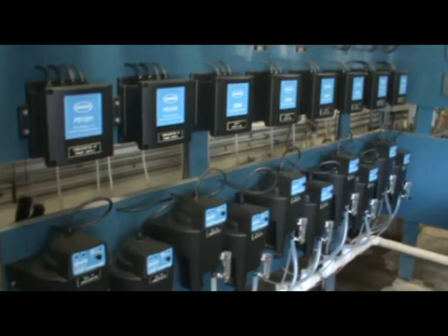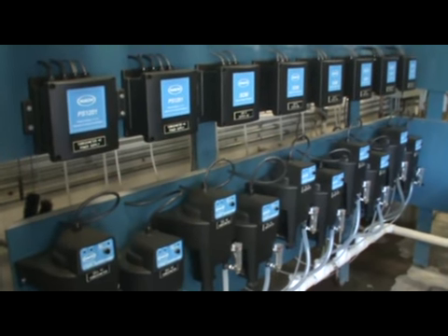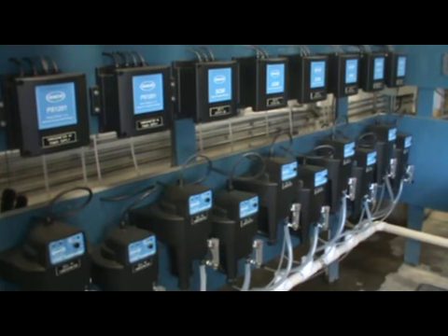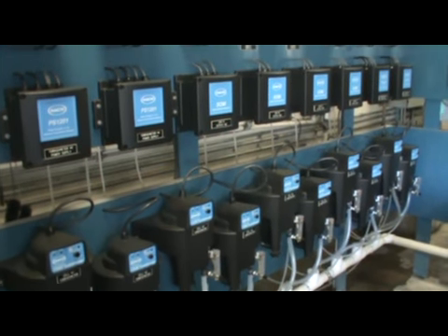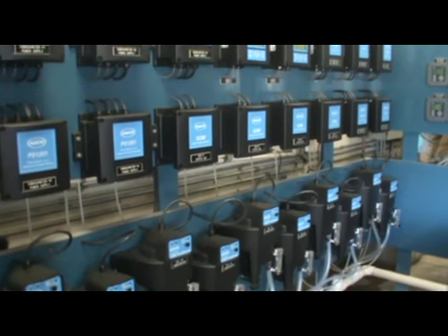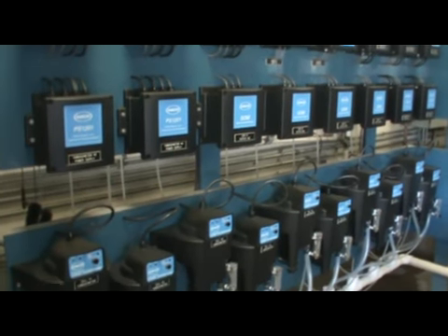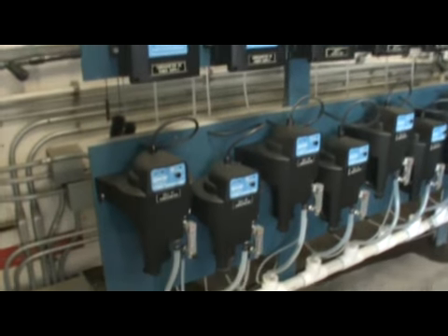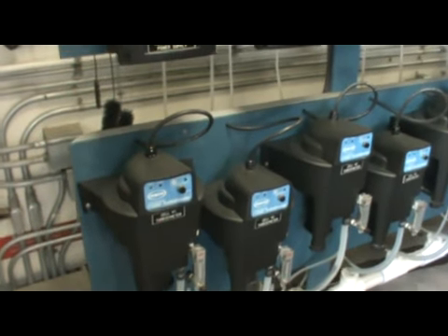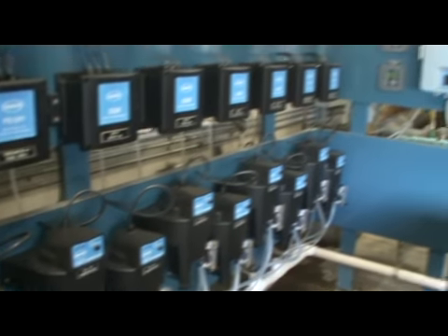Monitoring is an essential part of any water treatment process, and there's monitoring that goes on through the entire process. What we have here is a set of turbidity meters that can monitor the influent water, which they call the raw water, the effluent water or the treated water, and also every single one of those 8 filter cells has its own individual turbidimeter. Basically the water flows through here and it can tell you the turbidity and what's going on in each of those cells.